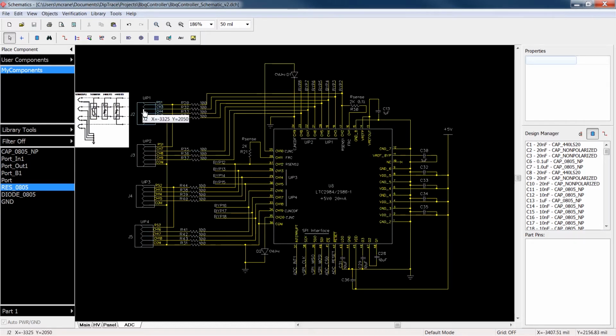So let's say UIP1, Universal Input 1, had the standard 2-wire RTD for the chamber probe, and input 2 had a 4-wire PT100 for the meat probe. If you wanted to change this one out to a thermocouple, the chip has to be reconfigured to support that. You can't just plug it in, it's not a plug-and-play type thing. The software is going to have to support it, it'll be like a drop-down to change them.